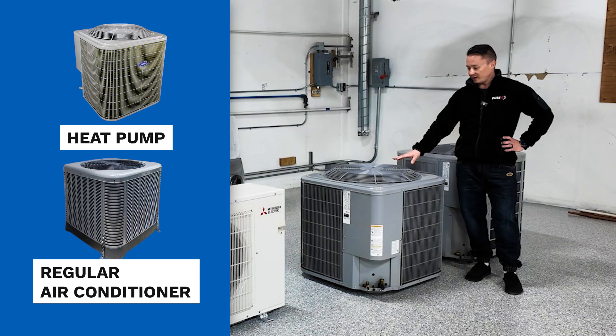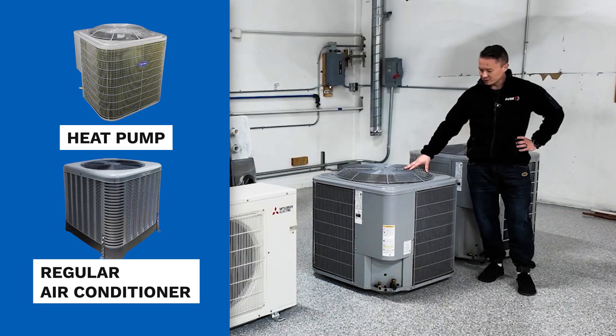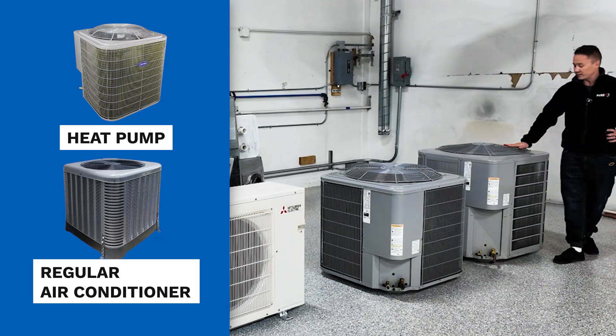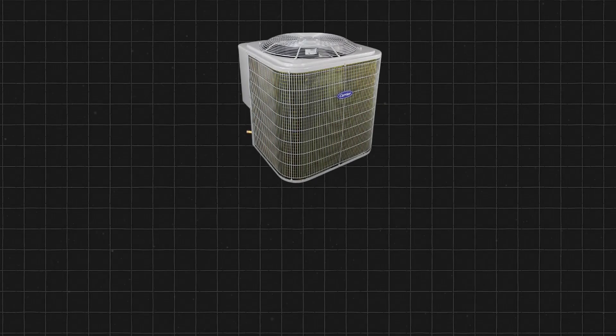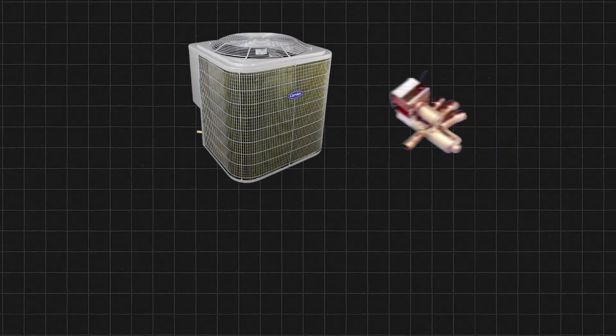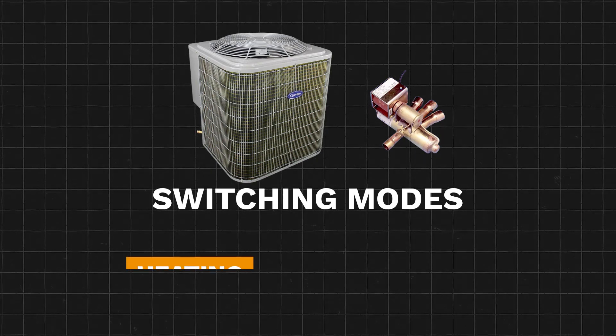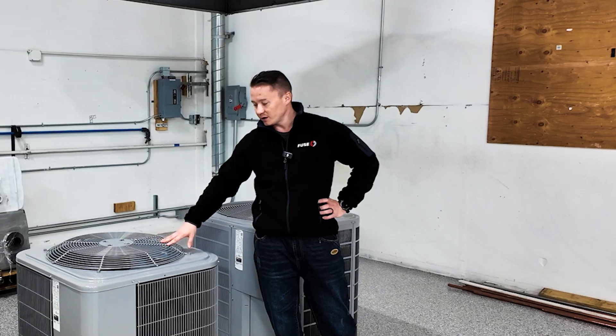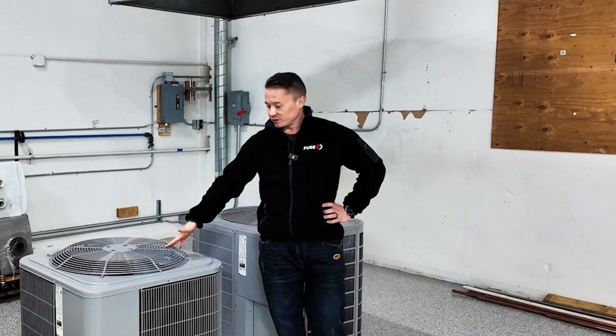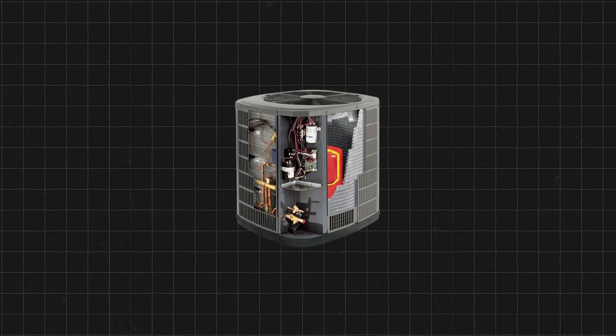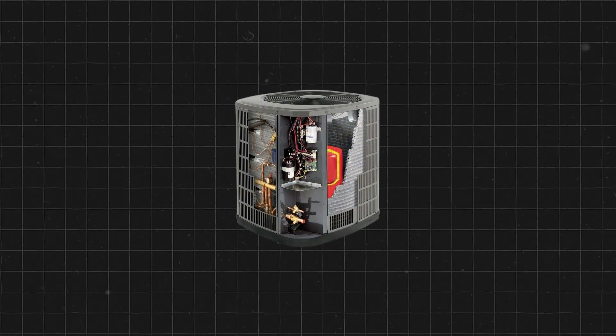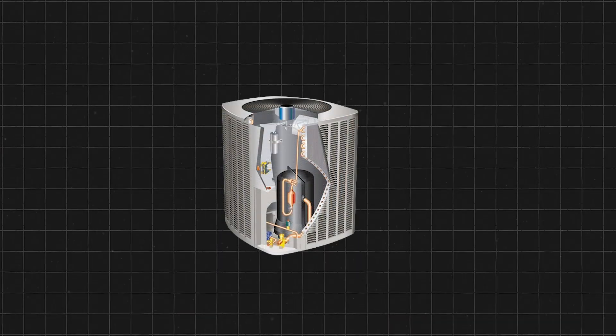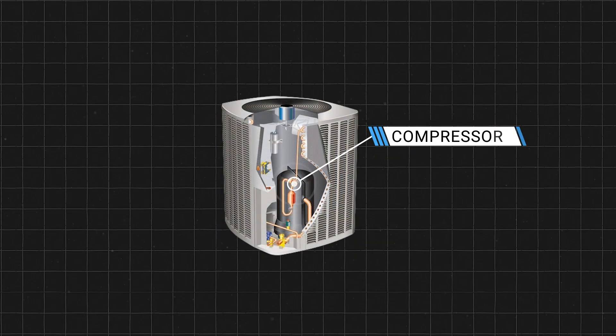This unit is actually a heat pump, and I know it because it has a few parts that we don't have in a regular air conditioner. A conventional heat pump unit like this has a valve which switches modes from heating to cooling — that's why this unit has the ability to deliver heating or cooling depending on the mode. Inside a classic conventional air conditioner, we have only one main part, which is called the compressor.